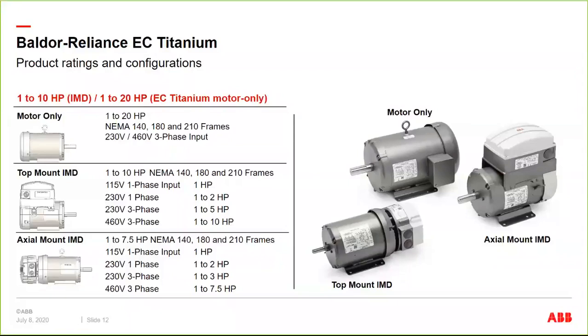In the top mount. But you can also use these as a phase converter because there is an integrated drive on there. If you're putting these into single phase applications in 115 or 230 volt, you could use this instead of a single phase motor as a phase converter and operate this across single phase power. And then you go three phase output to the motor itself. We do all that wiring internally for you. So we go up to 1 horsepower 115 volt, or 2 horse single phase 230 volt, or 3 phase up to 5 horsepower 230 volt.